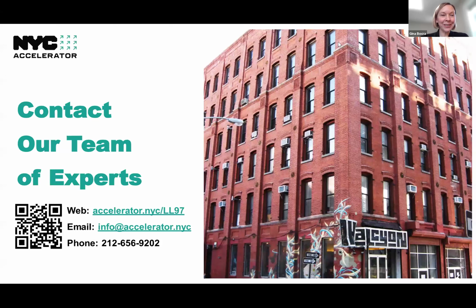Wow, that is why you should be working with someone to look at your particular building. If it complies with the code, it may be compliant with the lighting power density requirements of the code, and it depends on when you made those changes. So you should be referencing the code that was in effect at that time. It may not comply with the controls measurements that were required in the code at that time. And if you didn't update your controls when you updated your lighting, then you would be subject to the new control requirements under the current code. So you need to be working with somebody who really understands the control and lighting power density measures that are required in the New York City Energy Conservation Code.